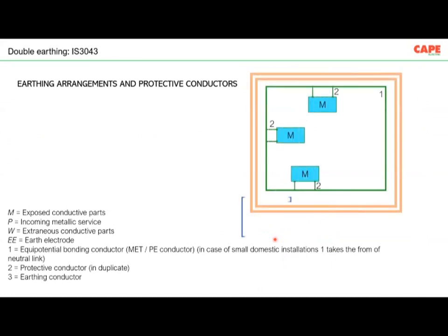Similarly, you can see this picture in IS 3043, which explains what exactly you mean by the equipotential bonding conductor. Number one is the equipotential bonding conductor. It is a bus bar which runs all around the building, which is supposed to be at zero potential. Now, M stands for exposed conductive parts. Three-phase equipment or larger equipment are supposed to have two connections in duplicate. You can see here two protective conductors in duplicate. So larger equipment are supposed to have two connections to the protective equipotential bonding, and this is called double earthing. Double earthing has nothing to do with two earth pits in soil. Double earthing means the exposed conductive parts of class one larger equipment are connected to the protective equipotential bonding with two connections.